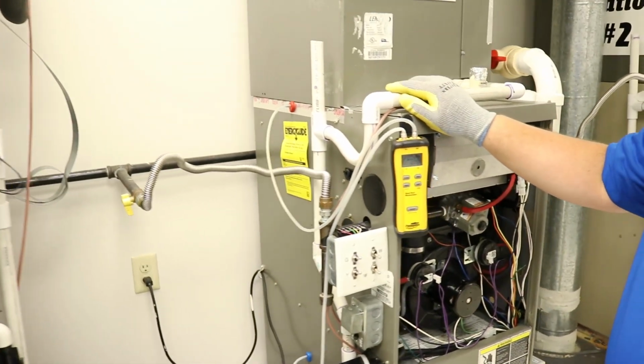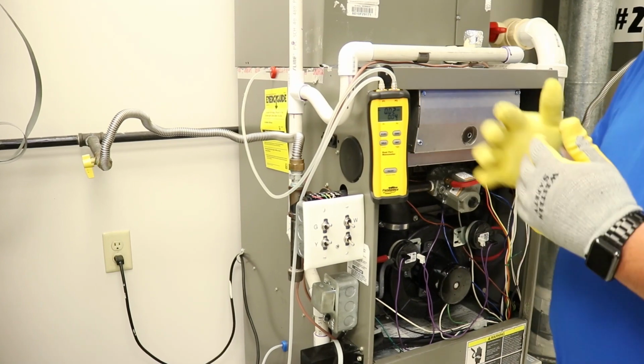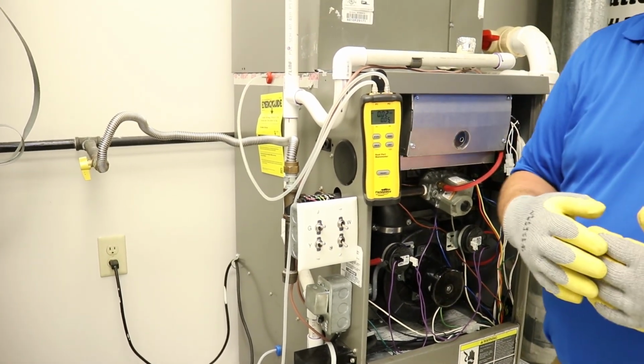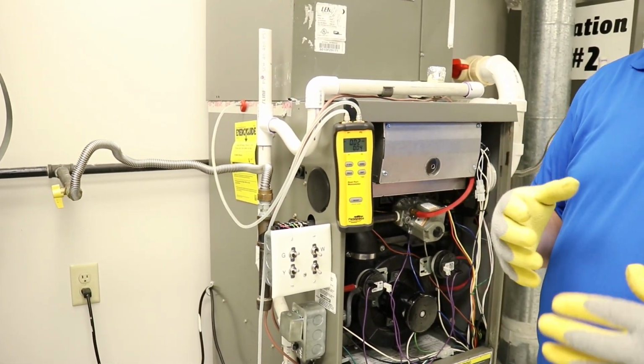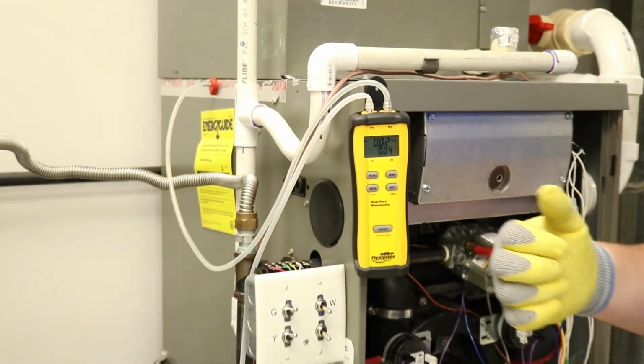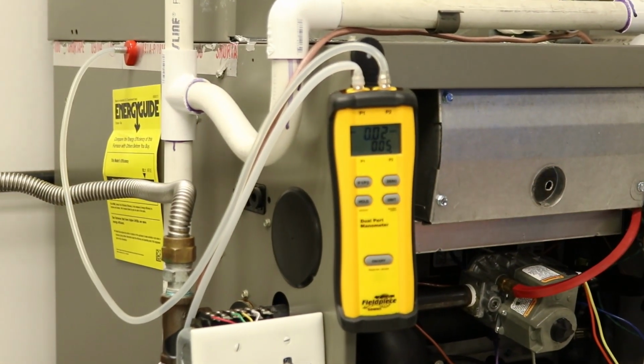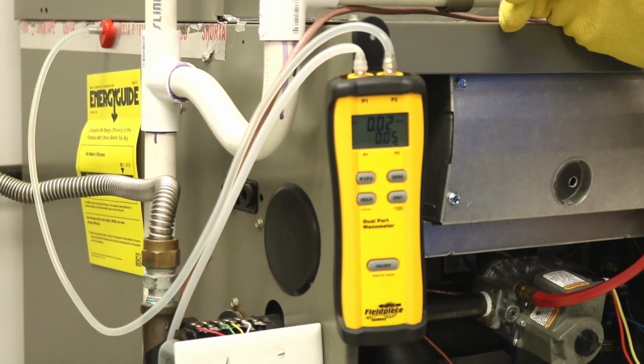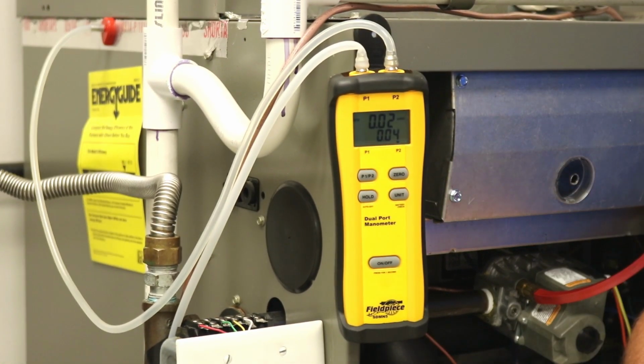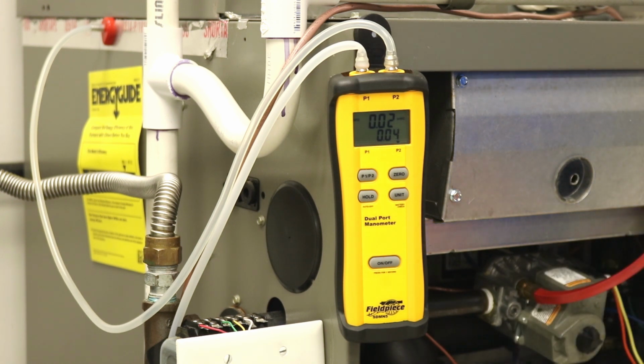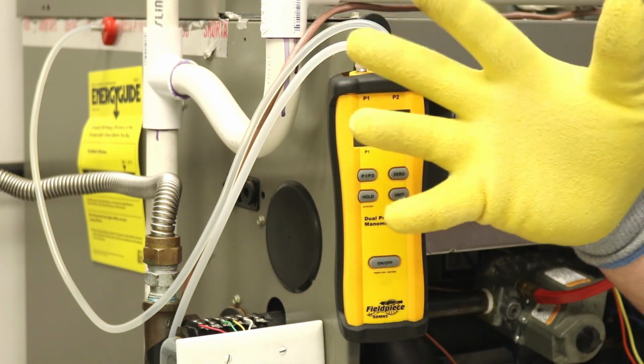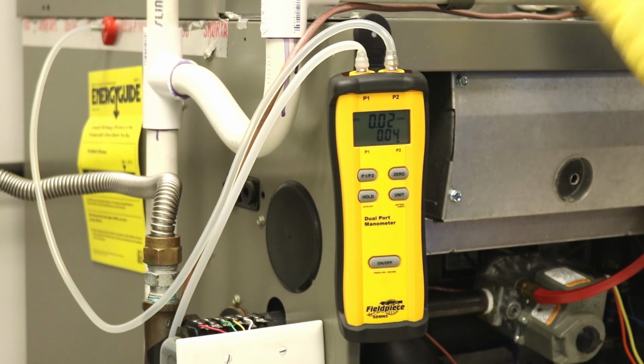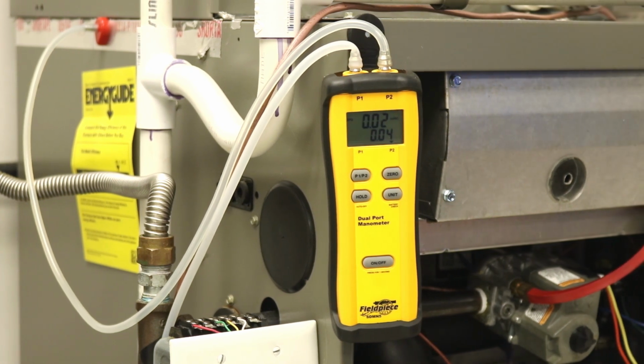The reason that is so important is because the evaporator coil and the filter are going to affect that static pressure. And if you're on the other side of it, you're not getting a proper reading. So let's make sure that, like I said, you keep it inside the box. Now for an air handler, your evaporator coil is a part of that box, so it's important to make sure that it's before the filter, by that blower motor. So making sure again that it stays inside that box. Don't go outside of that furnace cavity. Don't go outside of that air handler cavity.